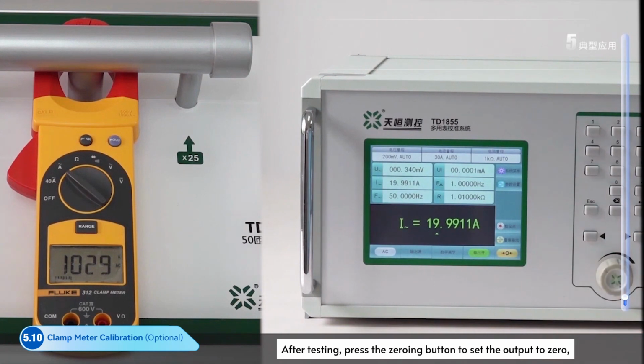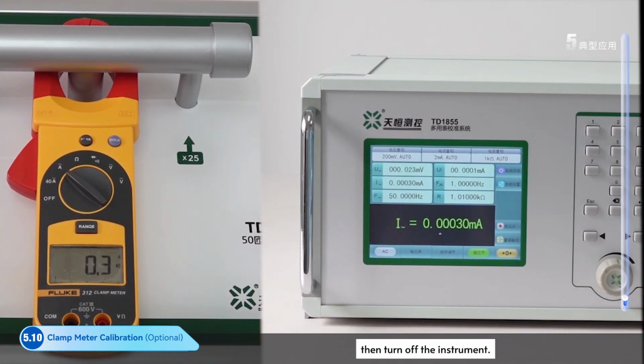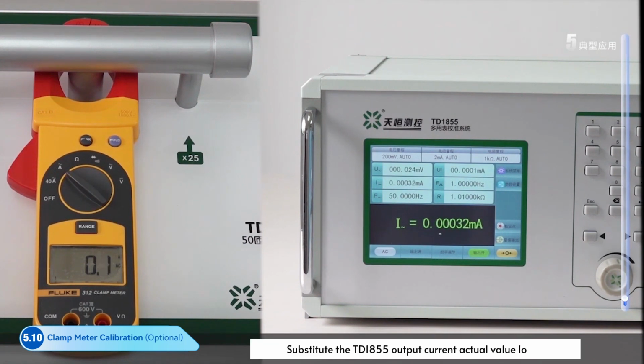After testing, press the zeroing button to set the output to 0. Then turn off the instrument. Substitute the output current actual value and the clamp meter's reading into the error calculation formula. Calculate the error for each calibration point and record it in the calibration report.